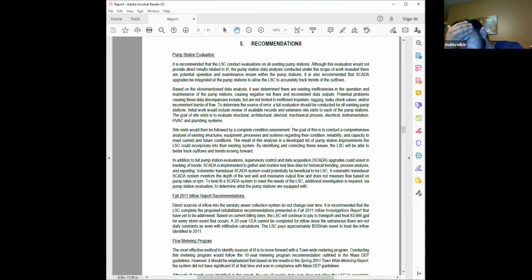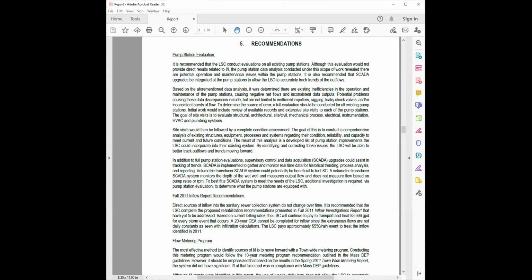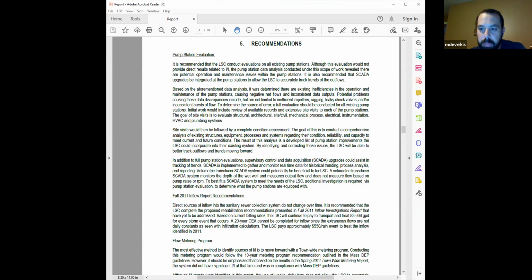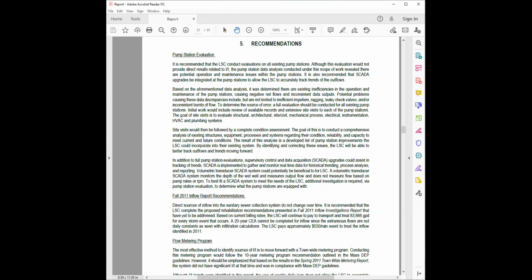With a PLC at each station, you could figure out the timing of when the pumps turn on and off. With a brand new grinder pump, if it takes 2 minutes to pump down 200 gallons, after 5 years does it gain 30 seconds, a minute? You could also tell when you need to rebuild your pumps, keeping an eye on pump efficiency.